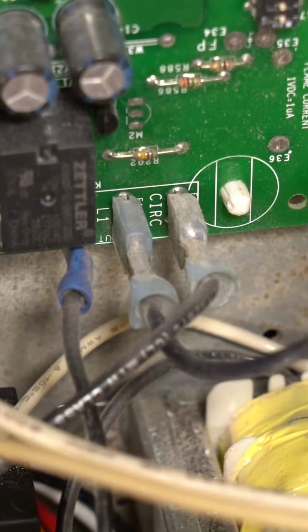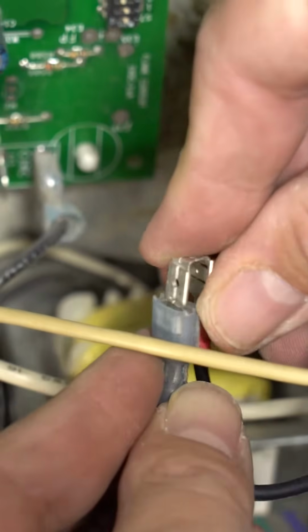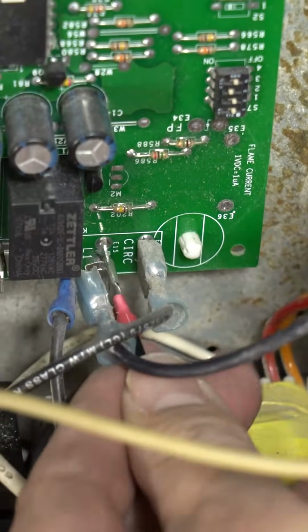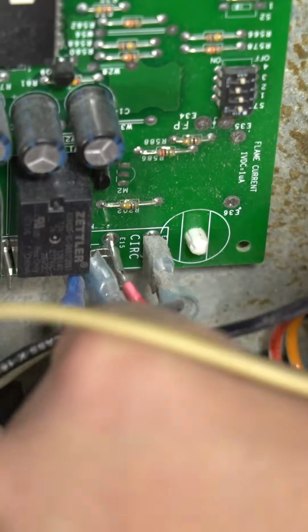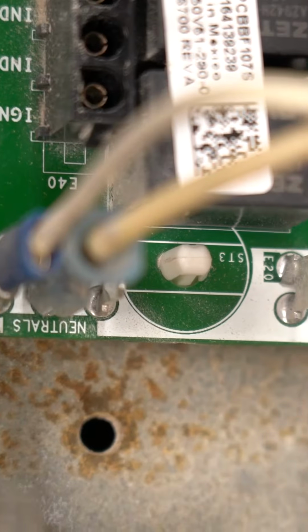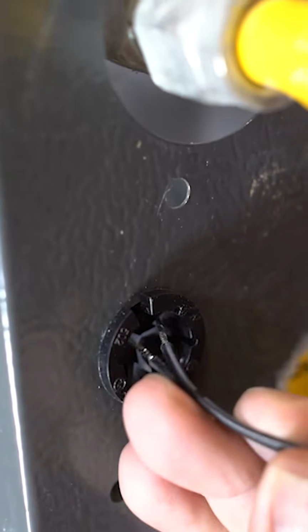Locate the L1 terminal on the circuit board. There's probably already a black wire connected. Disconnect that and connect the quick splice connector we attached to the black wire from the transformer, then connect the quick splice connector to the L1 terminal. Locate an open terminal on the neutral section of the circuit board and plug the white wire from the transformer there. When you run the power cord from the unit into the furnace cabinet, you need to use a plastic grommet to protect the wire.